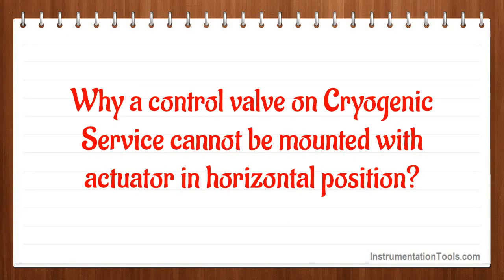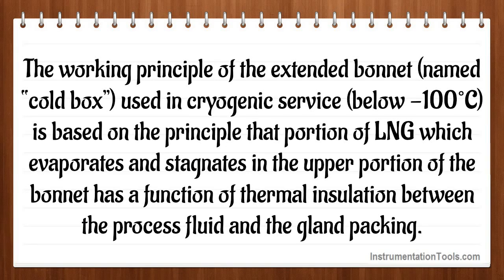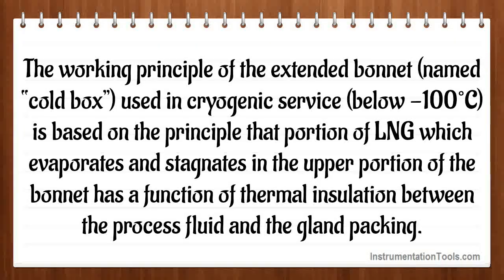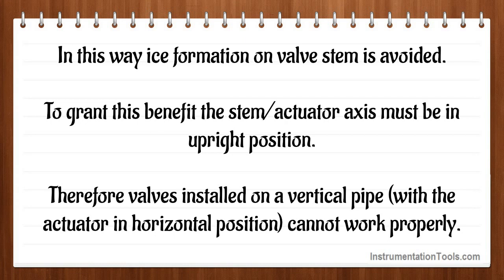Why can a control valve on cryogenic service not be mounted with the actuator in horizontal position? The working principle of the extended bonnet, named cold box, used in cryogenic service below minus 100 degrees centigrade, is based on the principle that a portion of LNG which evaporates and stagnates in the upper portion of the bonnet has a function of thermal insulation between the process fluid and the gland packing. In this way, ice formation on the valve stem is avoided. To grant this benefit, the stem-actuator axis must be in upright position. Therefore, valves installed on a vertical pipe with the actuator in horizontal position cannot work properly.